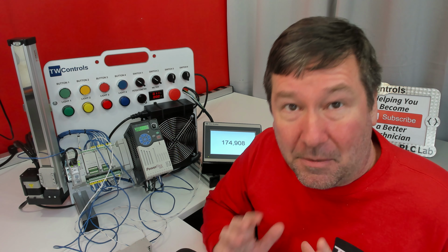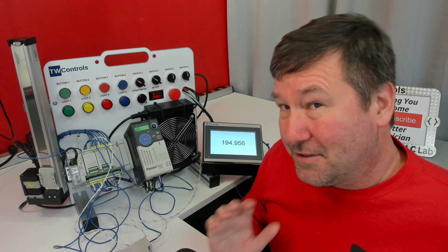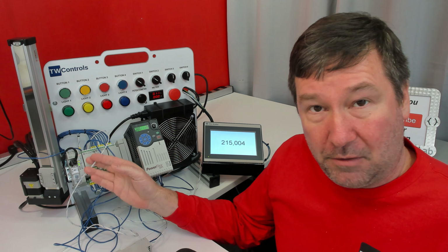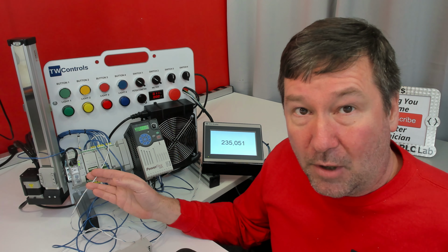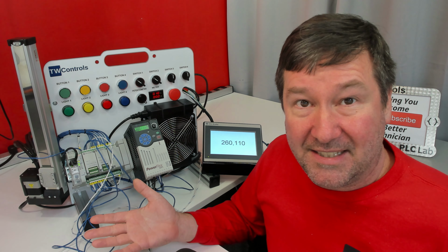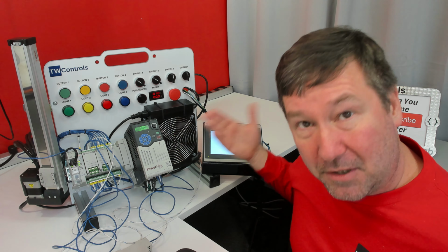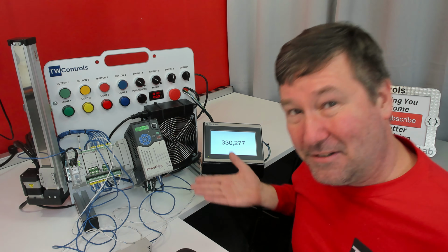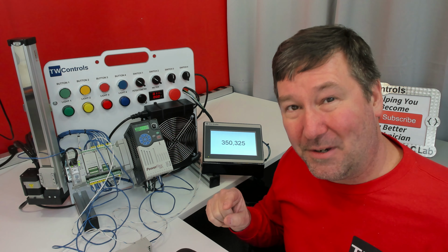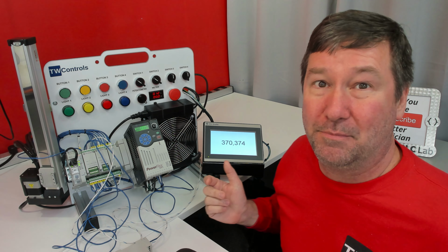The next thing we need to talk about is our rollover. And there's several different ways we can do this. We can roll over off of our Z marker, which is wired to our reset in the counter. If we had an up counter, such as we would have on a flow meter, the rollover is going to go to 0. If it's an encoder, it's going to go to a negative 2 billion.